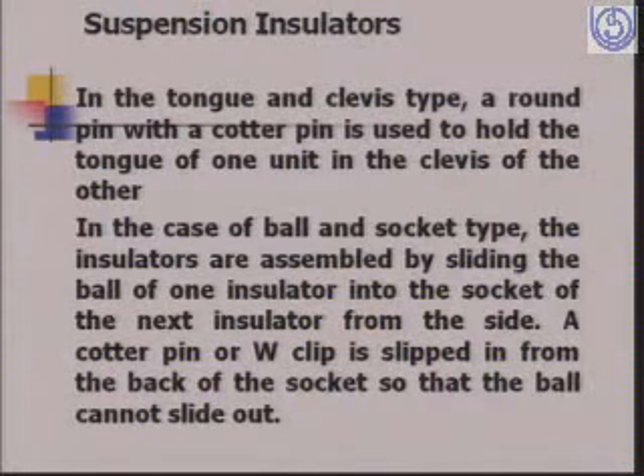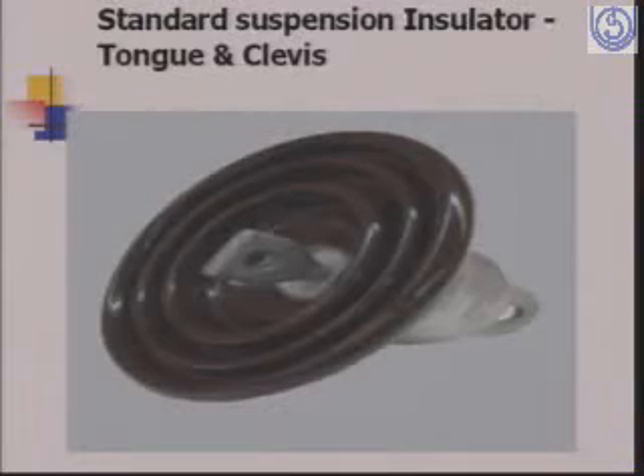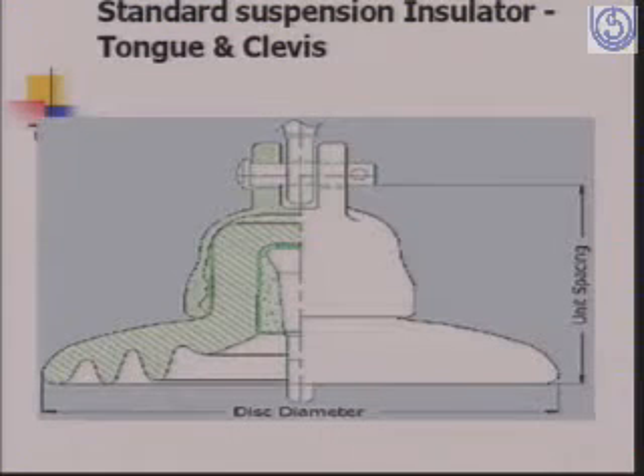So the suspension insulators in the tongue and clevis type, a round pin with cotter pin is used to hold the tongue of one unit in the clevis of the other. And in the case of ball and socket type, the insulators are assembled by sliding the ball of one insulator into the socket of the next insulator. This is a tongue and clevis type of insulator. You can see there is a tongue and there is a clevis. This is a tongue and clevis type insulator shown.